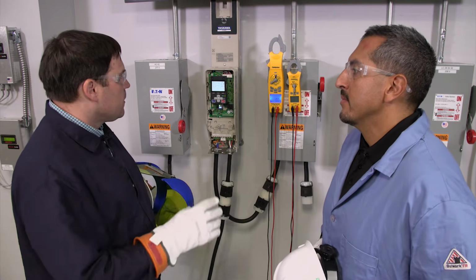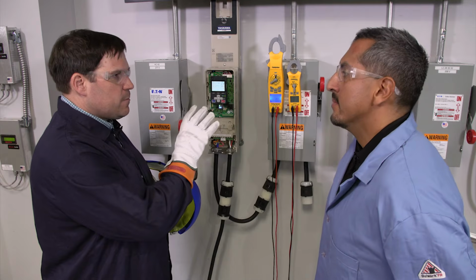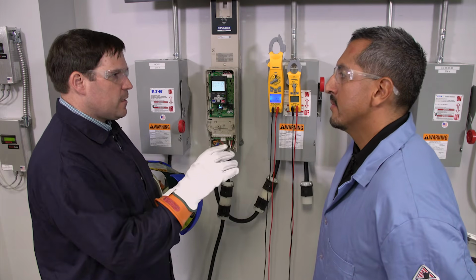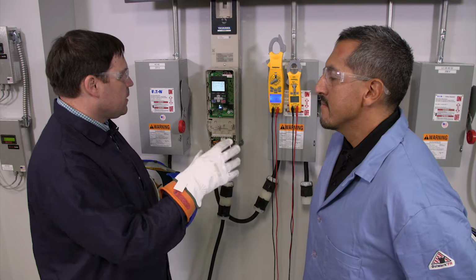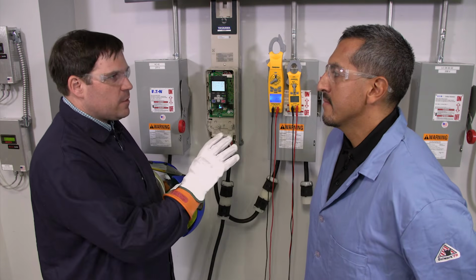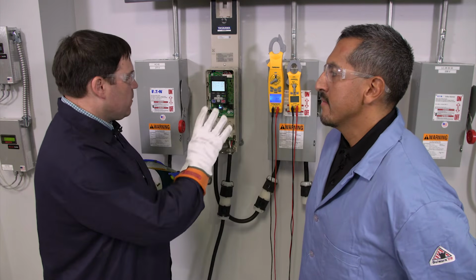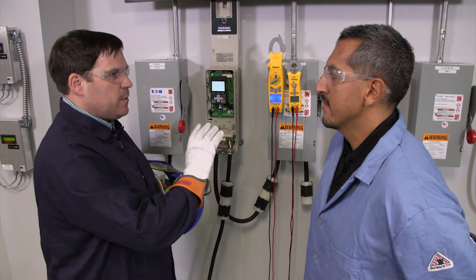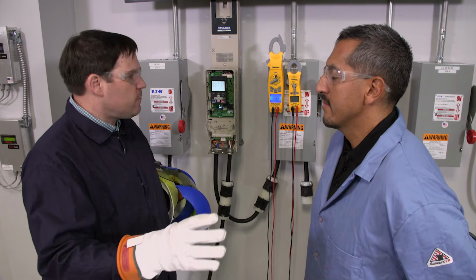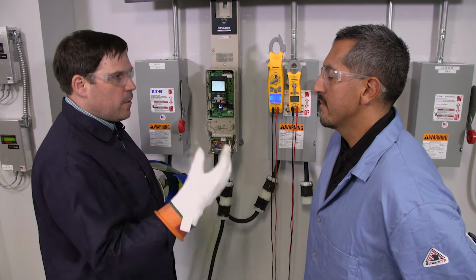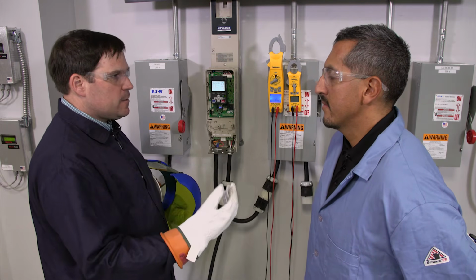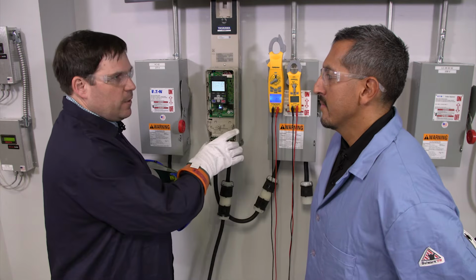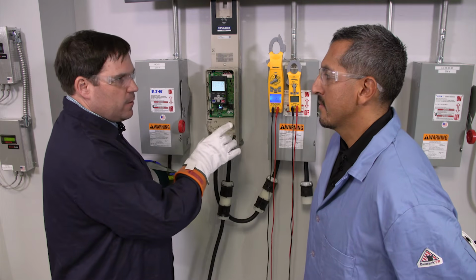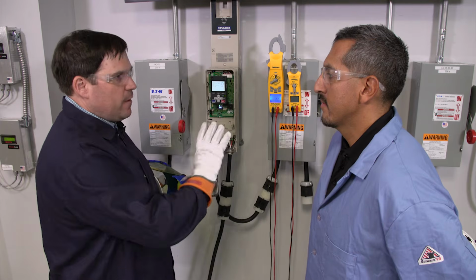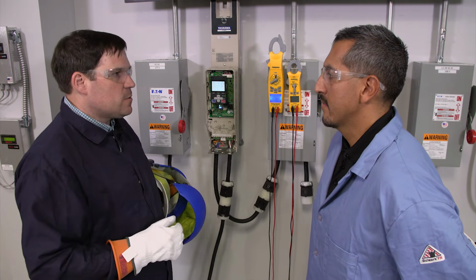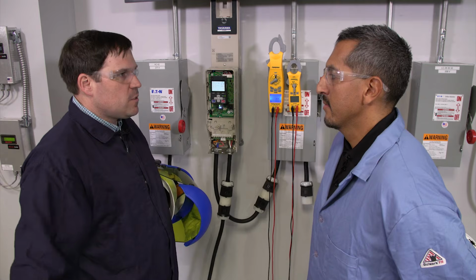That's a great question. When you're talking about a service perspective or an independent verification perspective—meaning testing and balancing or building commissioning—it's critical that we get the most accurate measurement. We could be troubleshooting this VFD, or the motor downstream of it, or from a verification standpoint we want a third-party, very accurate measurement to verify this equipment. That's why you'd want to use an external measurement versus relying on the drive itself.